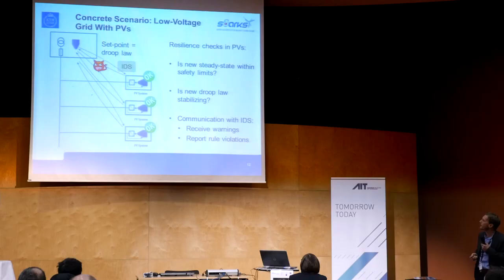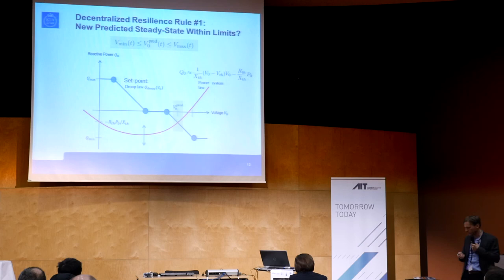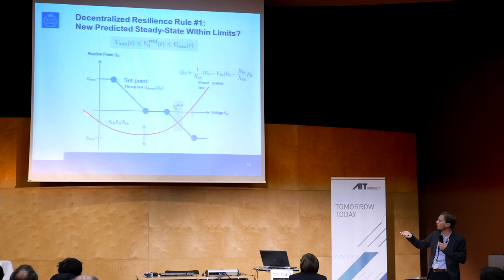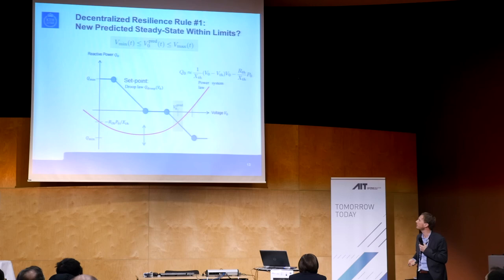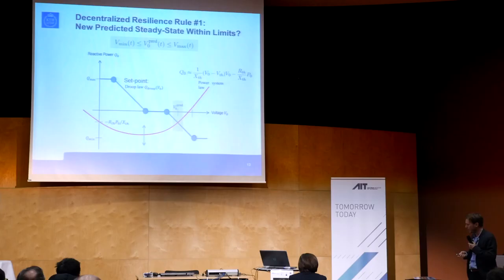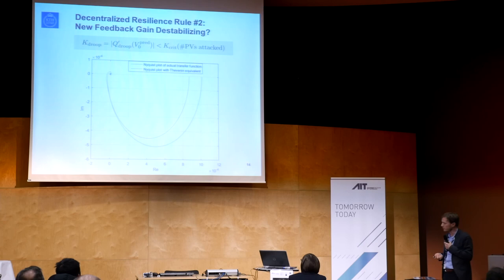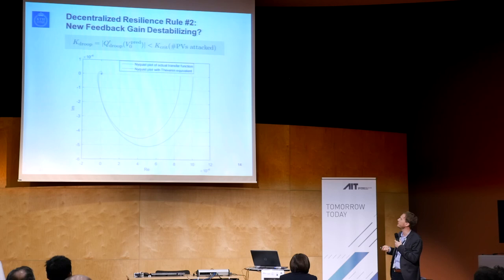Here's how the first rule works. The anti-islanding system gives you a simple model of the power grid. You receive a set point — that's the command. The crossing point on the curve is the predicted new voltage you would have if you implement that command. Is this within limits or not? If it's not, you don't execute it or you send a warning. That's the first simple decentralized test. For the second test, you use the Nyquist stability test to check the gain — basically the slope of this curve. If the slope is too high, you can get unwanted oscillations, as you will see in the demo.